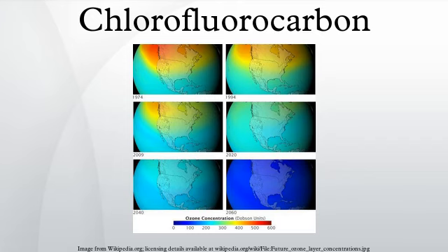Safety. According to their material safety data sheets, CFCs and HCFCs are colorless, volatile, non-toxic liquids and gases with a faintly sweet ethereal odor. Overexposure at concentrations of 11% or more may cause dizziness, loss of concentration, central nervous system depression and/or cardiac arrhythmia. Vapors displace air and can cause asphyxiation in confined spaces. Although non-flammable, their combustion products include hydrofluoric acid and related species. It is important to note that normal occupational exposure is rated at 0.07% and does not pose any serious health risks.